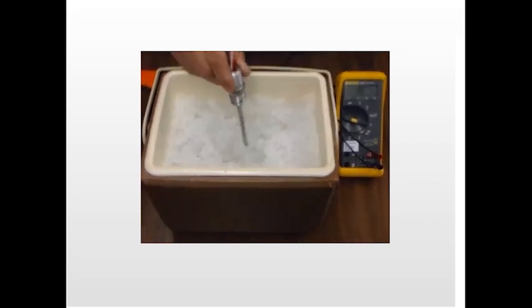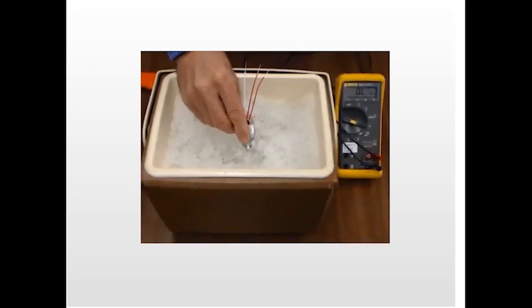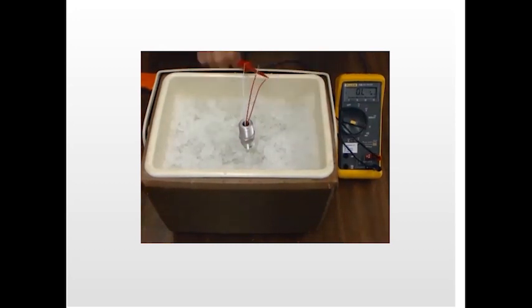Then we'll take our temperature probe and insert it. It's a good idea to insert it at least about 4 inches. You don't want it to touch the bottom of the bath. Then we hook up our lead wires, and here we're reading about 100.1 ohms. Now we want to eliminate the lead wire resistance. So we go over to the 2 red lead wires, and we're seeing about 0.2 ohms of resistance. If we subtract that from what we see between the white and the red lead, that gives us the resistance of just the platinum sensing element, and that's what we want.